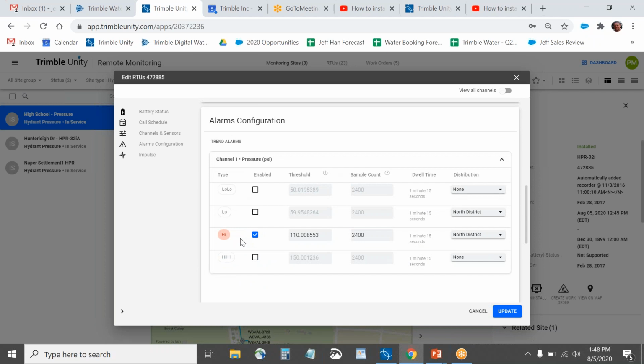We also have a simple tool to set alarms. This particular recorder has an alarm set so that if the PSI ever reaches 110 or above, the North District will get a text message and email. These distribution groups can be groups of people or individuals, and you'd see that in the list. So if a high alarm of 110 PSI happens, the North District gets notified by email and text.